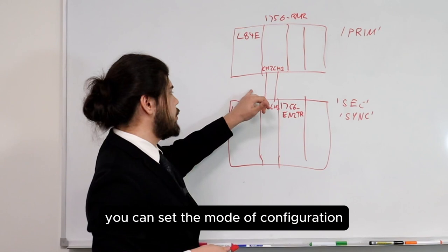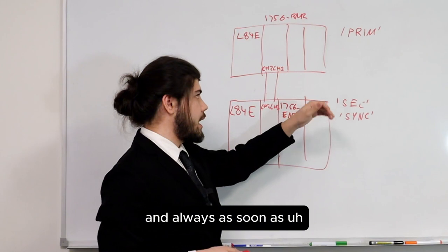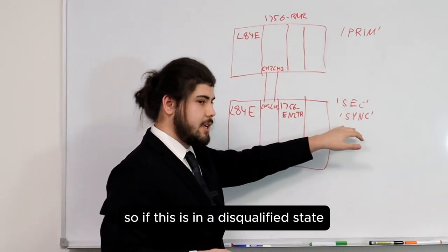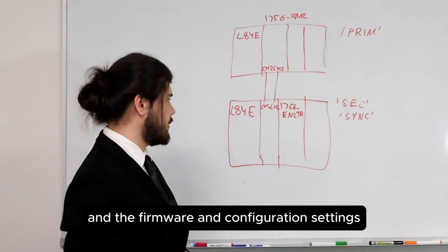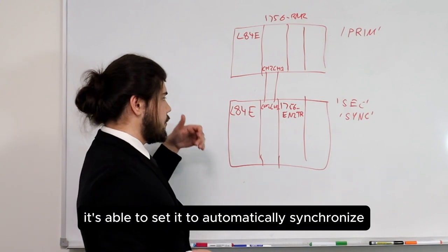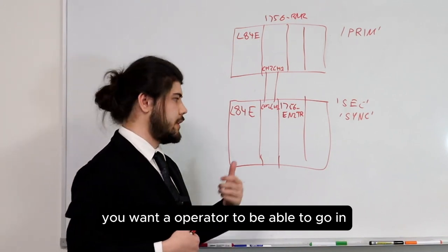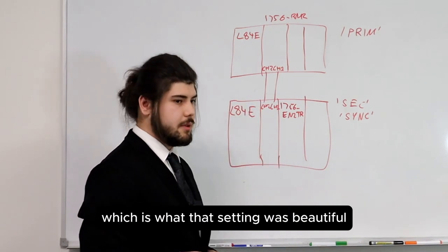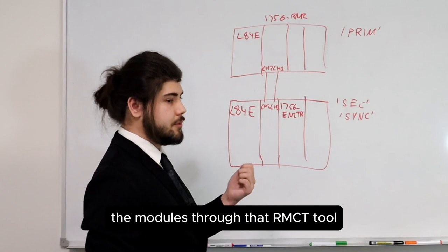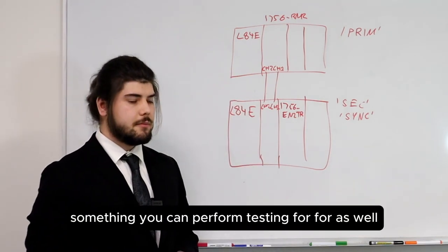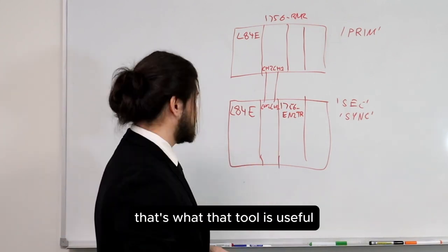The RMCT handles things like setting the mode of configuration such that it synchronizes automatically as soon as the connection is made. So if the system is in a disqualified state but is able to synchronize through checking hardware, firmware, and configuration settings, it can be set to automatically synchronize. That's useful if it's a remote site and something becomes disconnected — an operator can fix the issue and have it automatically synchronize. You've also got a 'never' setting for auto-synchronization, and you can manually synchronize the modules through the RMCT tool, which you can also use to initiate a switchover, qualify, or disqualify.